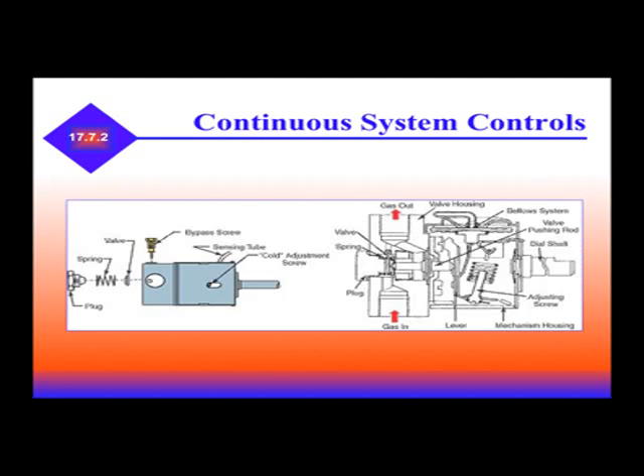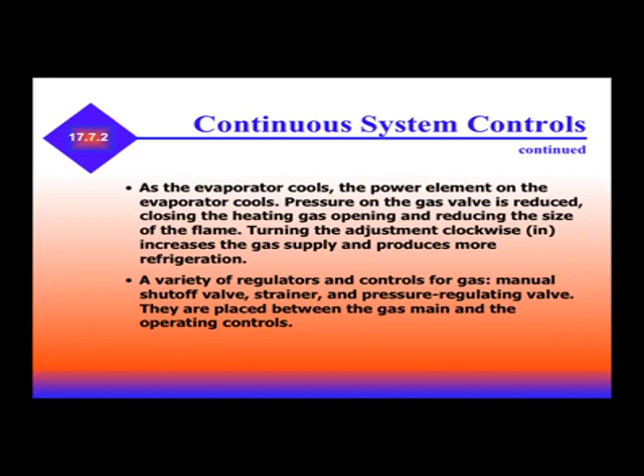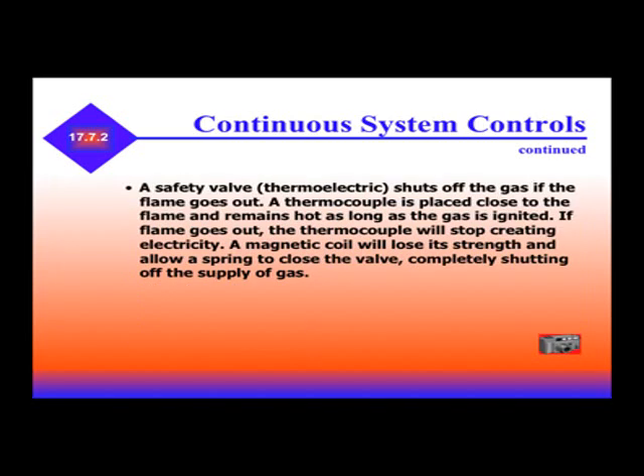On the left-hand side you can see the power element. As the evaporator cools, the power element cools, pressure on the gas valve is reduced, closing the heat gas opening and reducing the flame size. Turning the adjustment clockwise (in) increases the gas supply and produces more refrigeration. A safety valve shuts off the gas if the flame goes out. A thermocouple placed close to the flame remains hot as long as gas is igniting. If the flame goes out, the thermocouple will stop creating electricity, the magnetic coil will lose its strength, and a spring will close the valve, completely shutting off the gas supply.